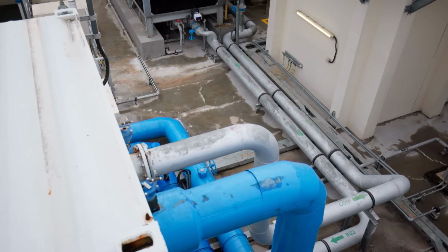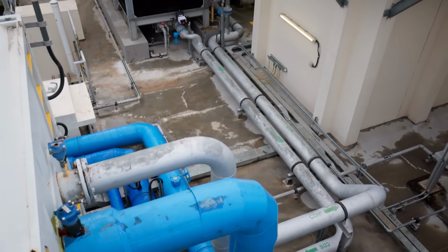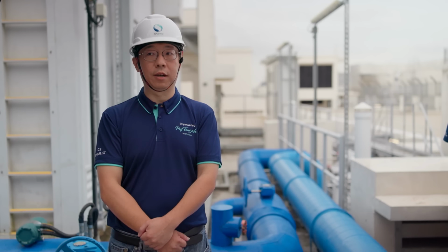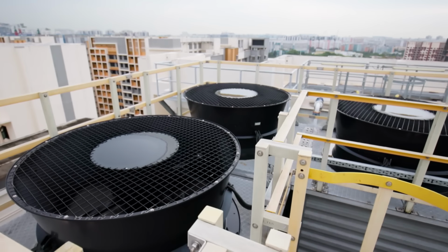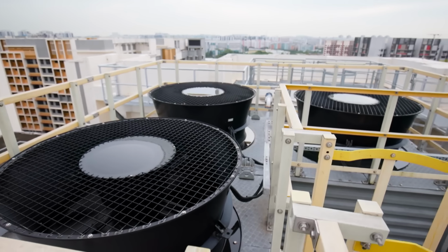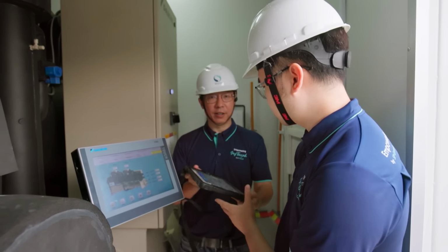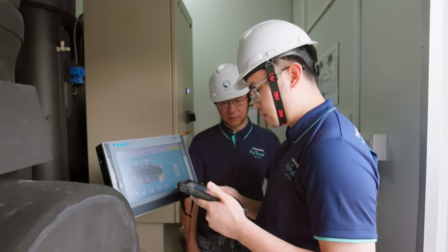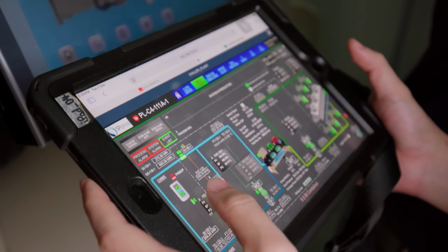The chiller cools down water by transferring heat from the water to its own internal refrigeration loop. This is then dissipated through cooling towers. This water-cooled process is much more efficient compared to the conventional aircon that our houses use.